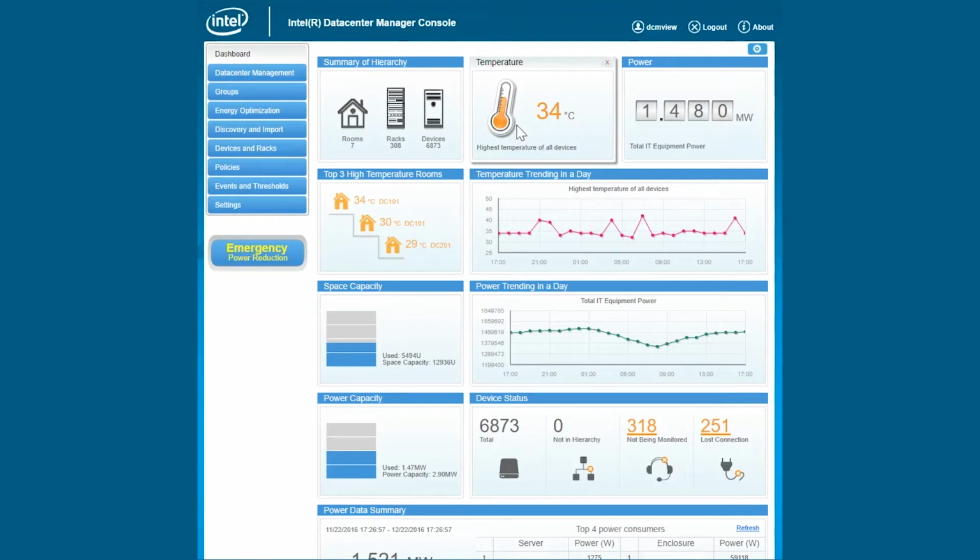and it uses these telemetries in order to help a data center operation manager to more efficiently manage the data center. Intel DCM connects to every device in the environment through the out-of-band solution of the device, meaning it is agentless. And then in real time, it collects information for the power consumption, the thermal status, and the health of the device. And then the software UI aggregates this information to a level that the customer will be able to consume this data in order to make sure he's managing his facility with the highest efficiency possible.